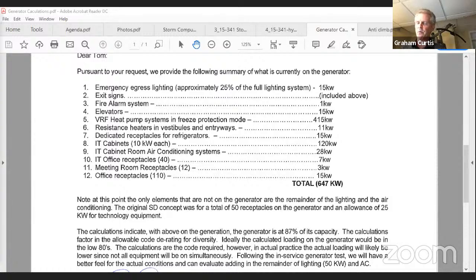We'll know better when we move into the building what the actual loads are as we operate. But traditionally, the calculated values are conservative, and in reality you see quite a bit less load. But the code mandates certain criteria. I'm expecting that the actual load in use will be less once we get the building fine-tuned operationally.